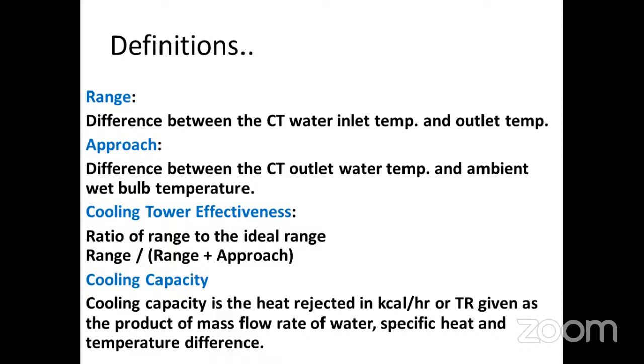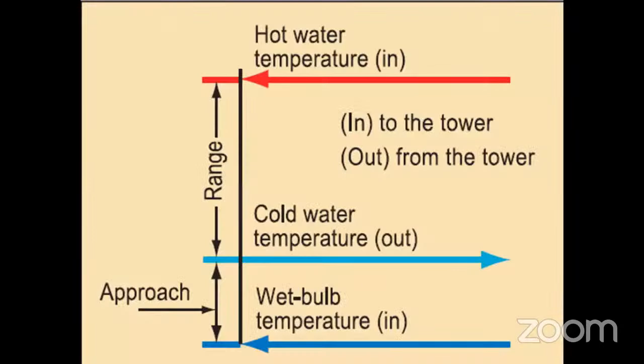What is cooling capacity? Cooling capacity is heat rejected in kilocalorie per hour as given in the mass flow rate of water, specific heat and temperature difference. Just keep this in mind, sir. This is hot water temperature. That is the temperature coming out of condenser that we have to cool. Right, sir? That may be in the range of 38 degree to 40 degrees centigrade. On the cold water temperature, if it is 38, this will be in the range of 30 degree, or ambient wet bulb temperature is recorded in the room with a wet wick in the tip of the thermometer.